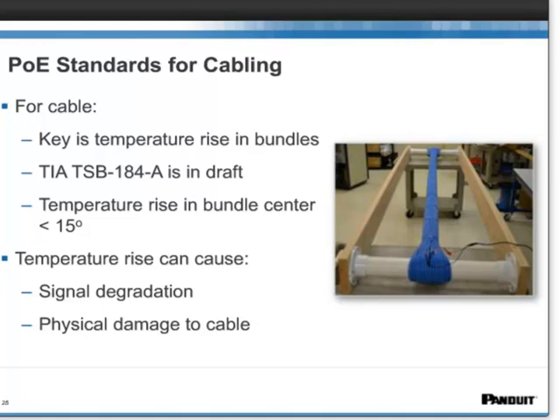TIA has developed TSB 184A to provide guidance on PoE installations. But the most important thing to remember is this: when you're bundling cable for PoE use, the center cable in your bundle cannot experience a rise in temperature of more than 15 degrees Celsius from the ambient temperature. If you're not mindful of this temperature rise, you're risking potential signal degradation and actual physical damage to your cable.